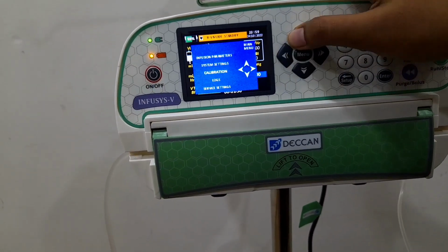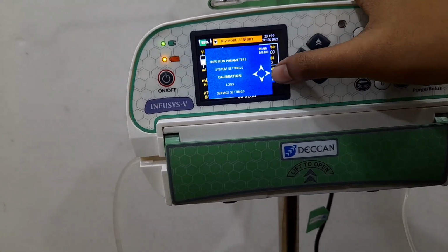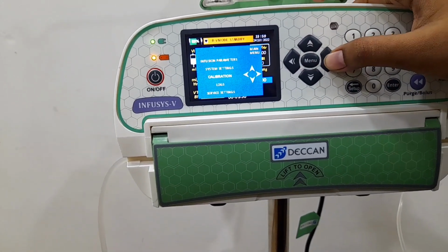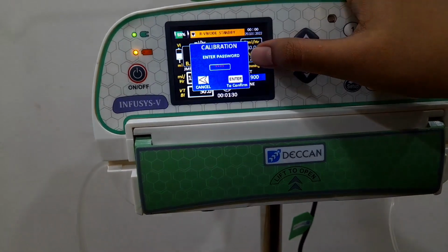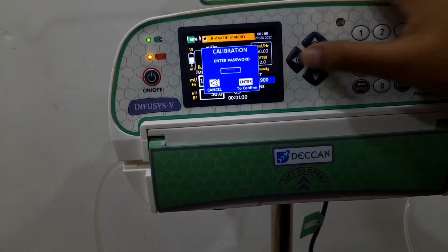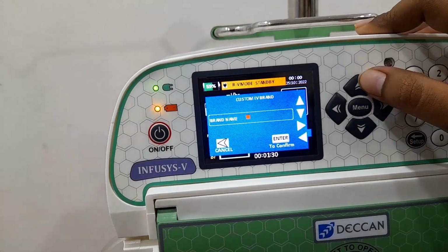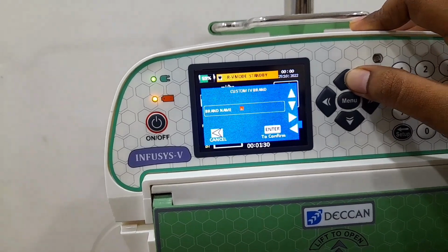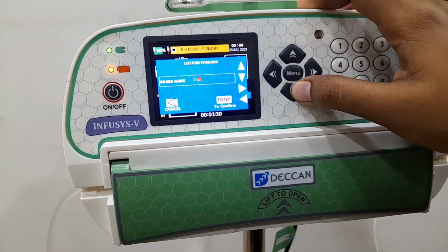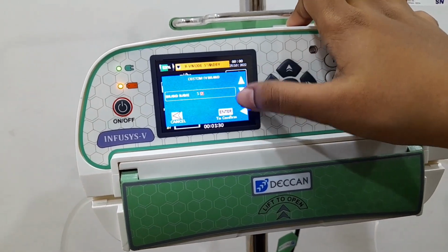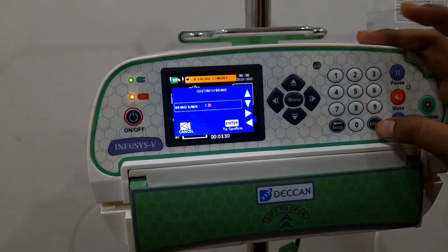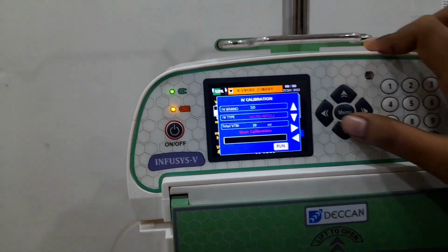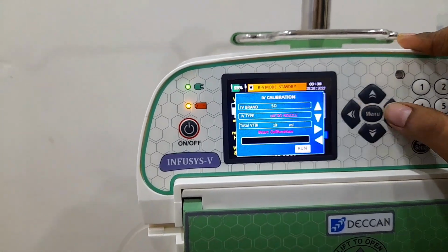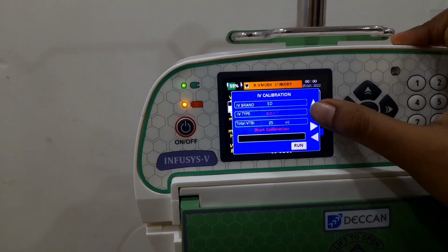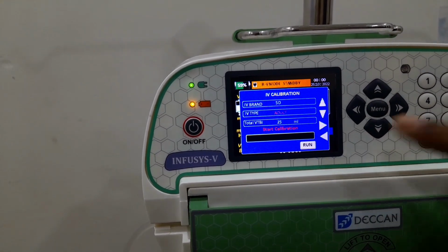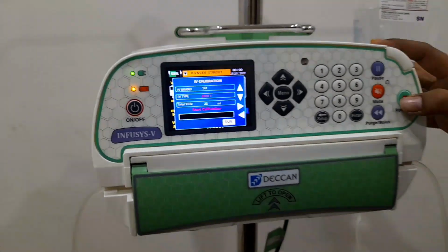Then we move to the calibration. Calibration is password protected. After entering the password, press enter to confirm. To enter the IV set brand name, press down key for alphabets and up navigation key for numeric values. Once we set the IV set brand name, press enter key to confirm. Here we choose the IV type as adult, microneedle or micronozzle using right navigation key. Here we selected adult. Press run as tab key to start the calibration.